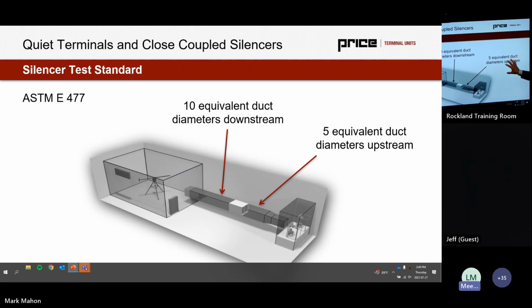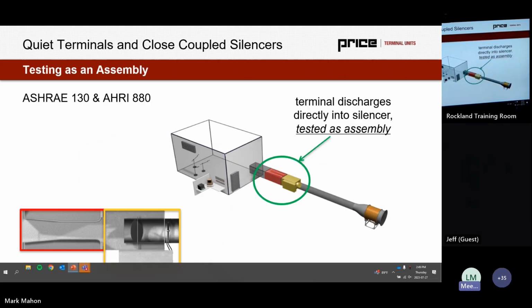Now, critically, this test method also has 5 equivalent duct diameters of straight duct upstream and 10 equivalent duct diameters of straight duct downstream. Fortunately, good silencer manufacturers will have rules of thumb that will help adjust the criteria for bad inlet conditions. And usually you get effectively the same performance as long as you have 2 equivalent duct diameters of straight upstream rather than 5. Or you can use an elbow silencer, which helps to eliminate these concerns as well. Now, when we test as an assembly, we just put the whole assembly together and measure how much sound it generates. We don't worry about insertion loss. We're trying to make a quiet terminal, not a loud terminal with a silencer behind it.